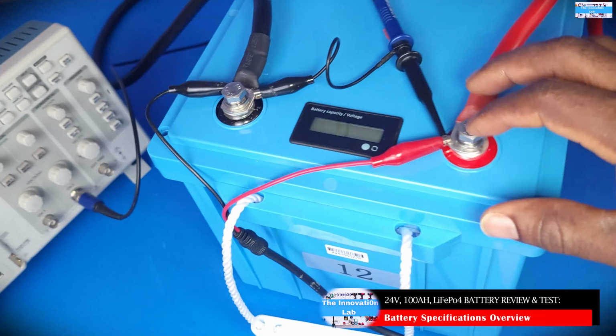But one thing we had to do, given that this is going to be a long duration load test, was to move the test load away from the test setup, because we don't want the radiated heat coming from the test load to heat up either the battery system or the power inverter system. One thing I would say is that even though the battery system is slowly discharging, meaning that the battery voltage is going to slightly drop and drop, I saw that using the power inverter system actually helped to stabilize that load and compensate for that voltage drop by increasing the delivered current coming out of the battery system and going to the power inverter. So that helped us maintain a steady state power draw of about 950 watts.